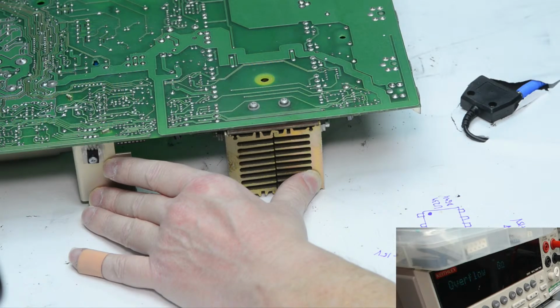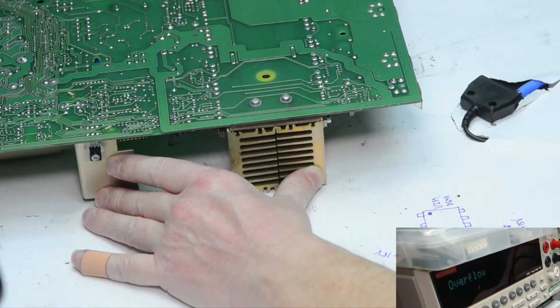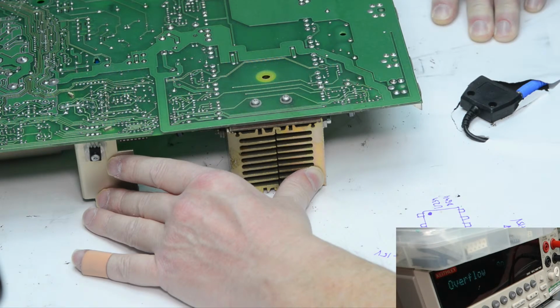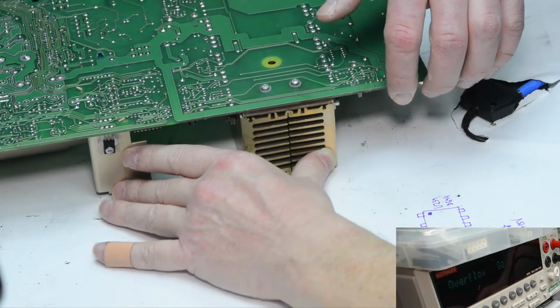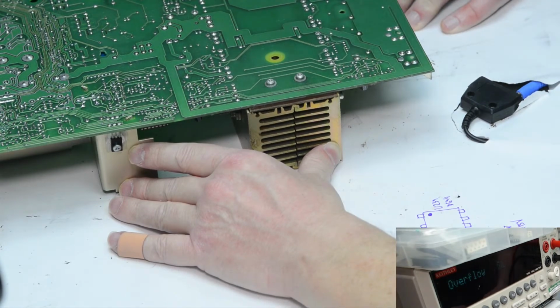Yeah, you can select the ESR. Don't have that one, so how do you do that? You do measurement parameter. You normally check at 1K or you check it at 120 hertz? Can you connect? What is it supposed to be? 100 mic? 100. ESR, so it's series, so RS should be. Try changing the frequency to 120. 120. 100, 120? Yep. Close enough.